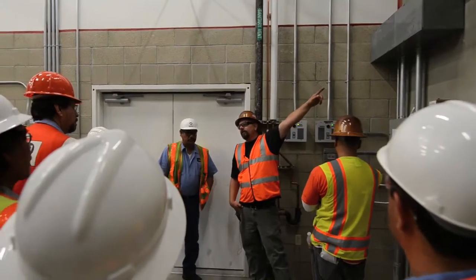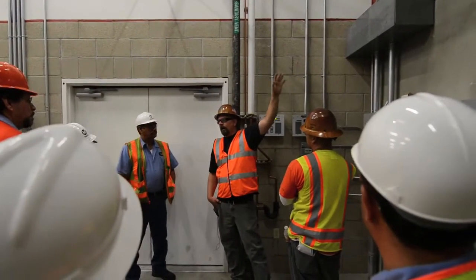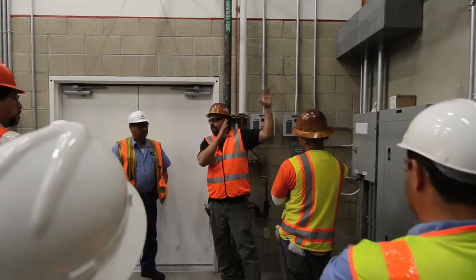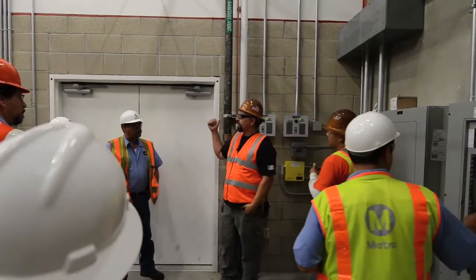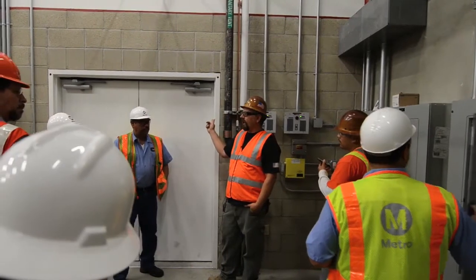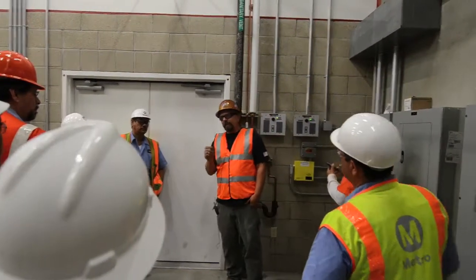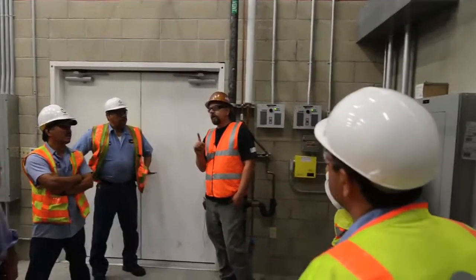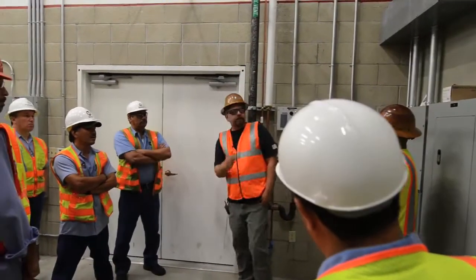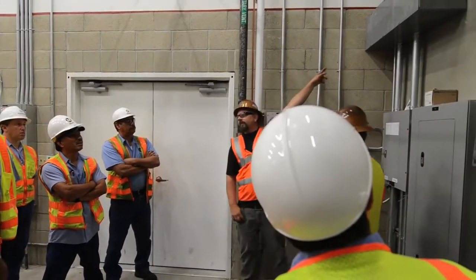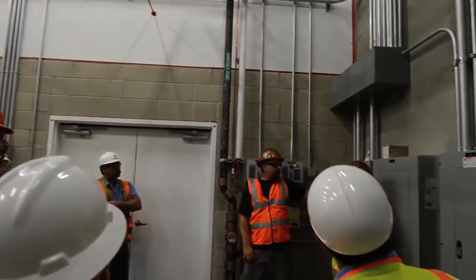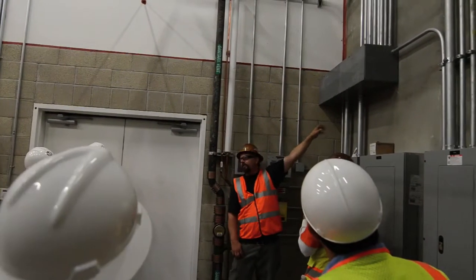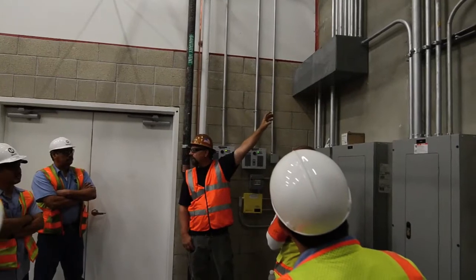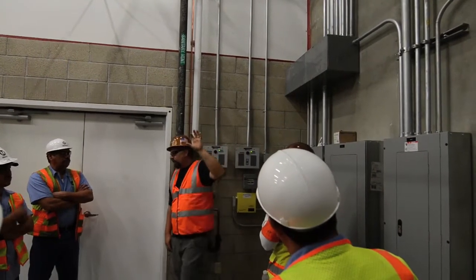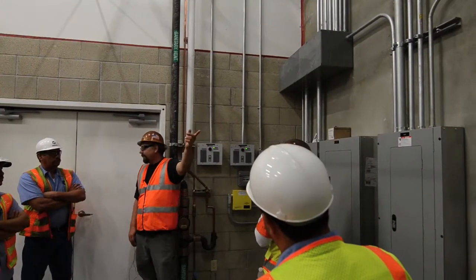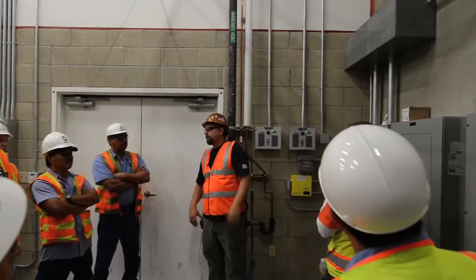Lights on the southwest lot, those are 480 volt. For whatever reason, those lights are 480. The lights on your southeast lot and northeast lot are 277. Because of that, I got one 480 circuit going out to that lot, and I've got a contactor up here inside this gutter. This lighting control panel is controlling the coil of that contactor for that 480 circuit going out. That's the only difference between those. They look like the same lights as you have everywhere, but they're not.